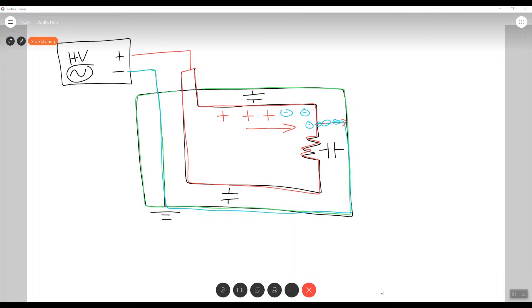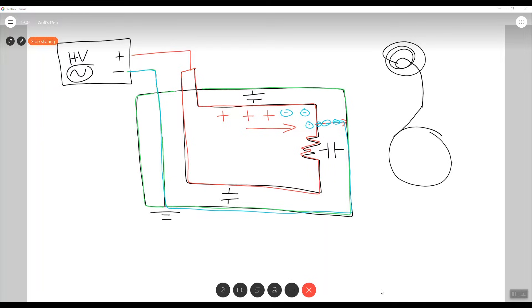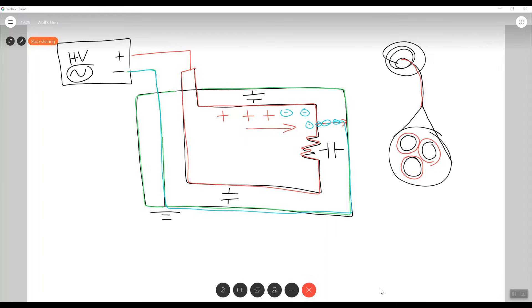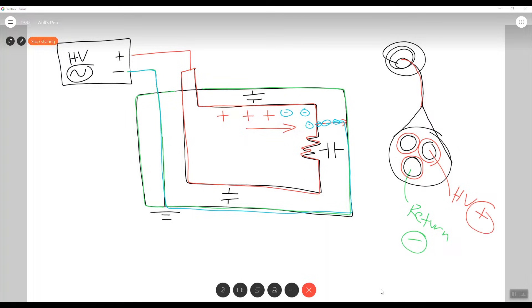That's why when manufacturers test spools of cables, all they're really doing is — if we take a cross-section of what's happening — these cables have various conductors inside of them, and those conductors all have insulation around them. How do you test to make sure through the entire spool there are no kinks, no cuts, no places where the insulation has become weak? You'd set one side to high voltage, the other as your return — your low side and your high side — and again, that electric field is now in between these spaces checking for any leakage.